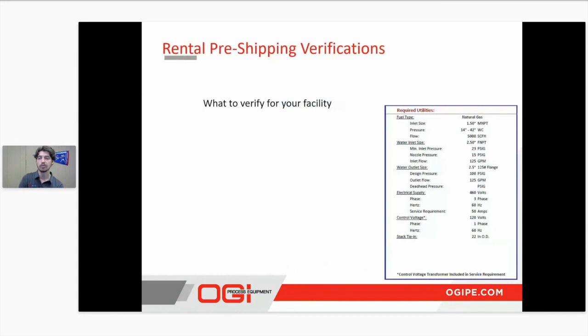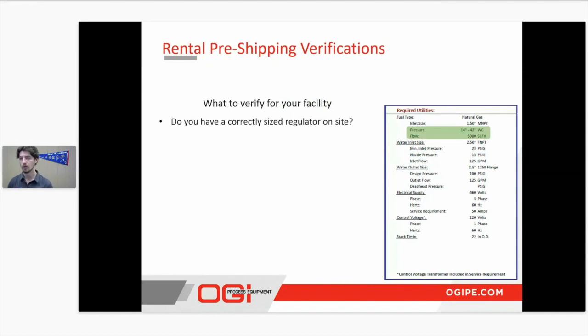A couple of important rental pre-shipping verifications for each facility. To start, we'll make sure that you have a correctly sized regulator on site for this unit. You can find that here. On each rental unit, you will have a specification sheet listed that I'll send. For this specific example, we have our pressure listed as 14 inches to 42 inches water column at 5,000 SCFH. You want to ensure that the regulator you have sized is going to work for this, especially if you have a low NOx burner attached on these units. They tend to be a little more finicky with the pressure going into them.